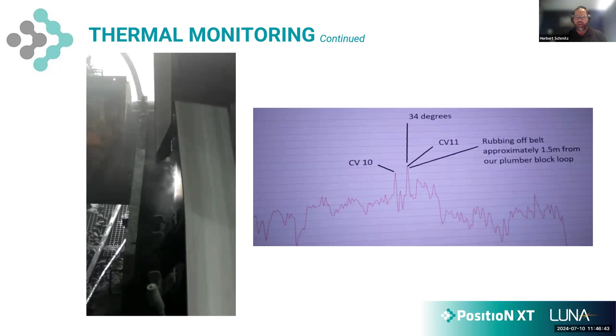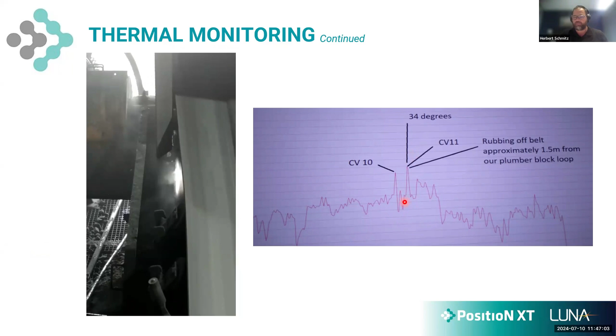As you can see, the smoke and the thermal energy coming off that very hot pulley, and how effectively we measured that incident. The technician then pulled the pull key, tripped the belt, and called maintenance personnel to come and investigate further. This is more than enough for us to be a delta over average, a hotspot indication to trip a hot belt.